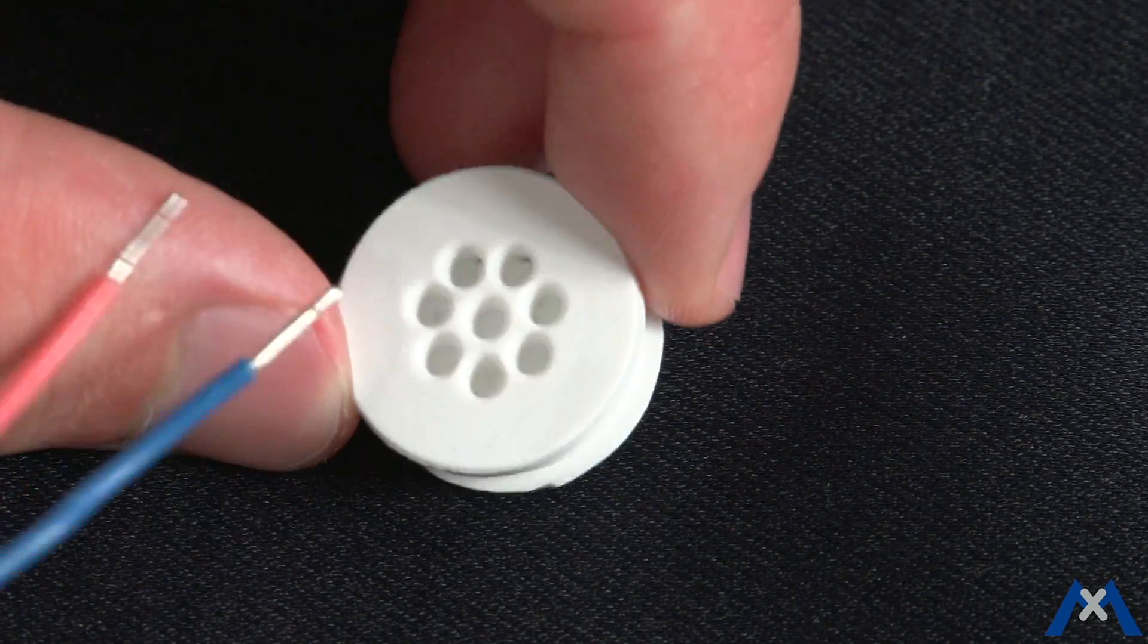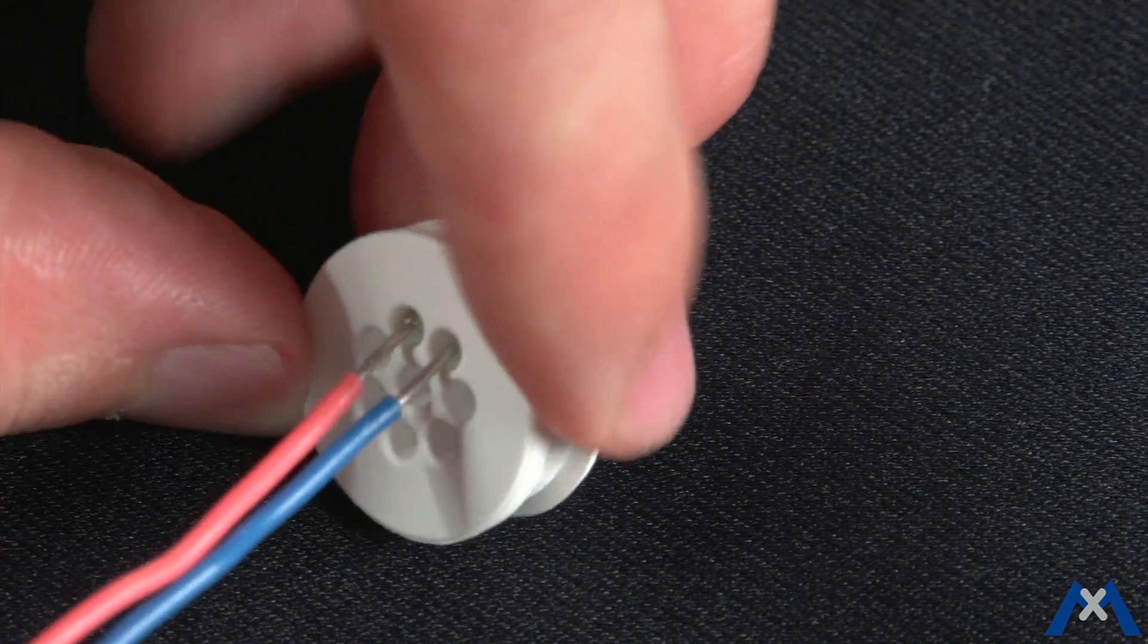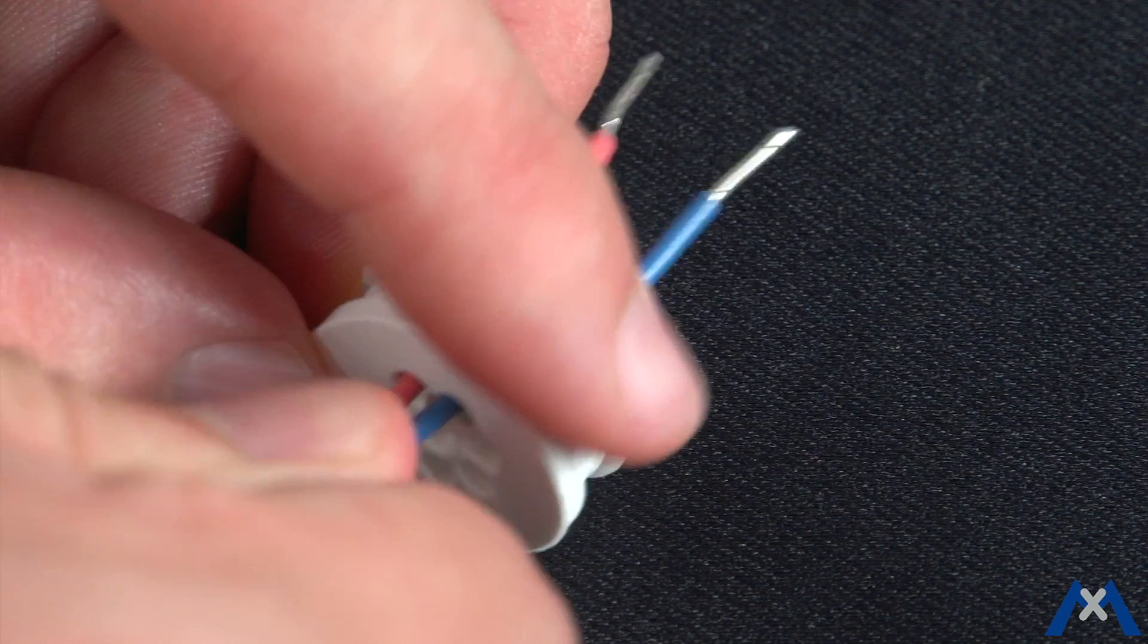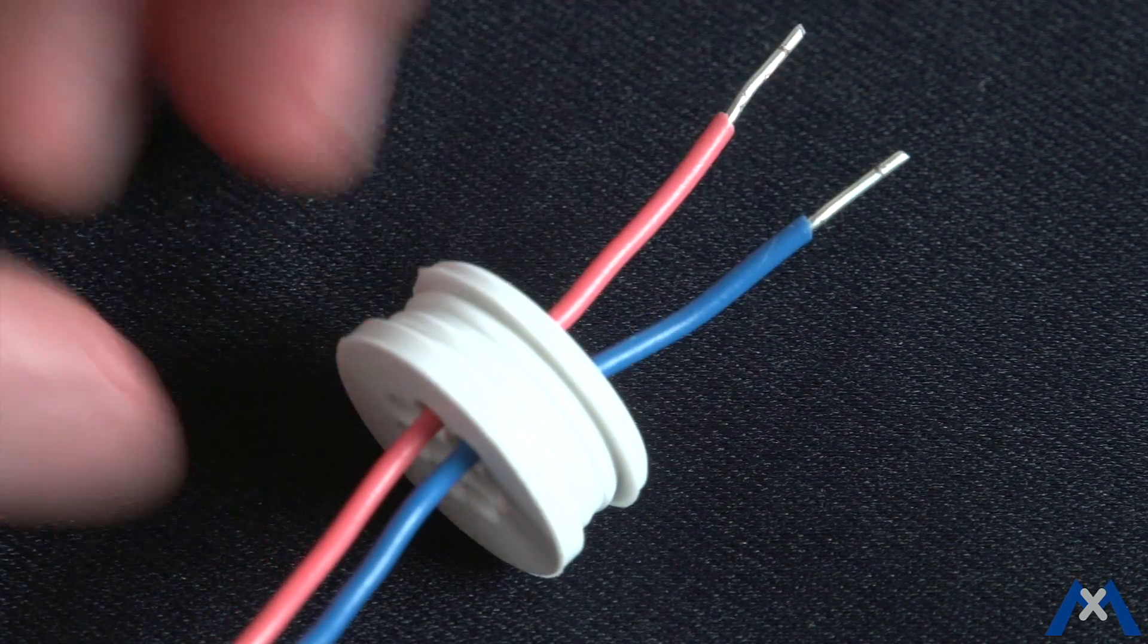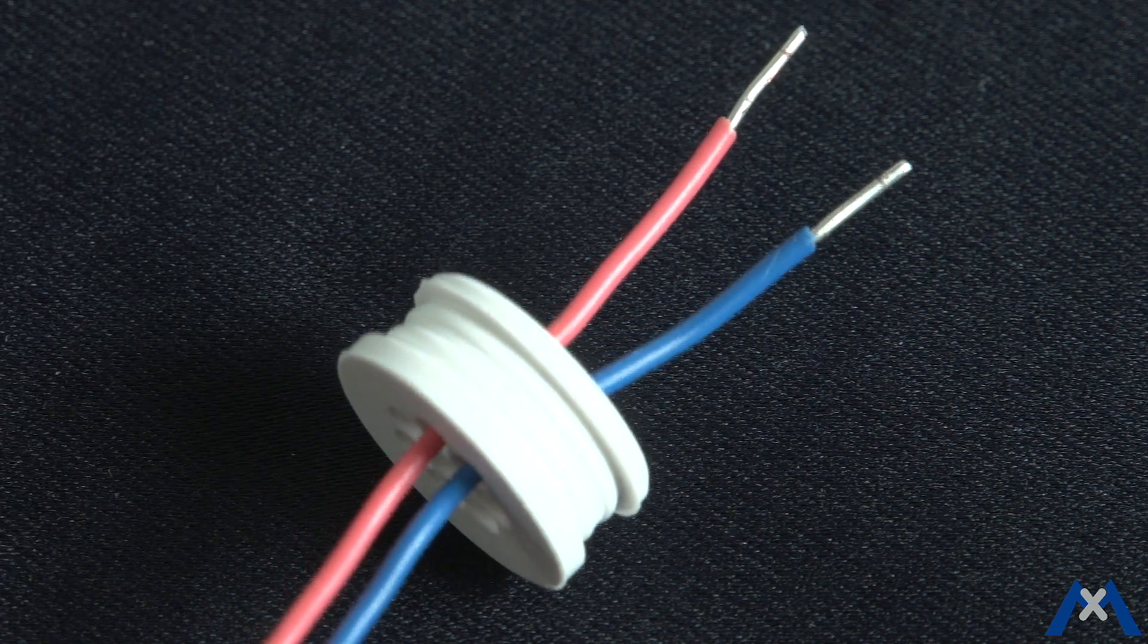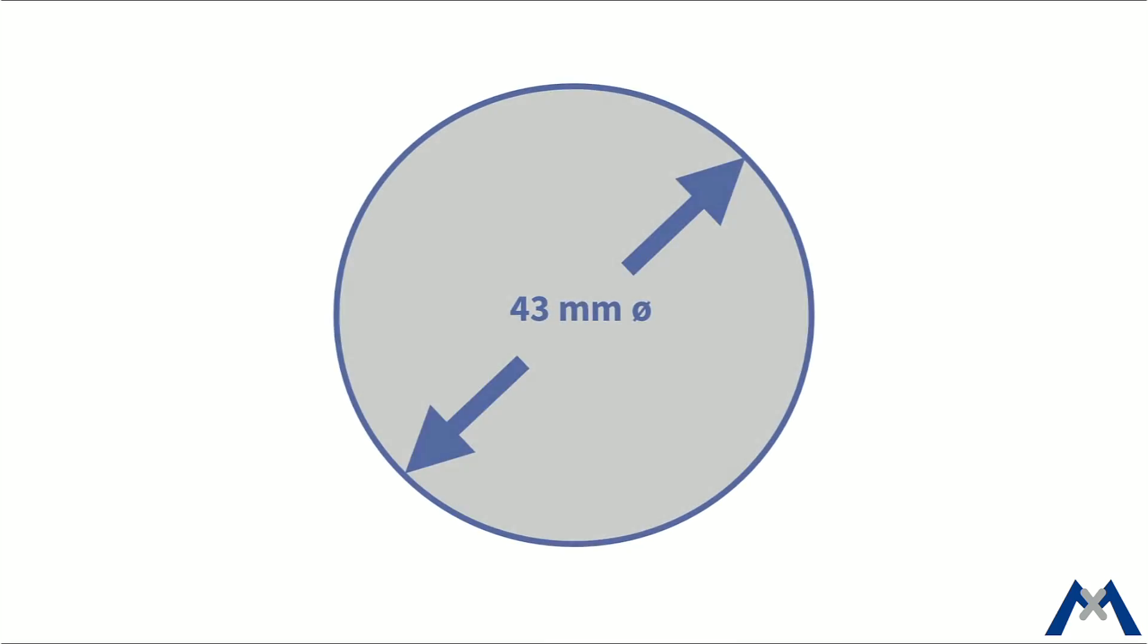If you are using the single wires, push them through the single wire plug. If you want to install the module in cavity walls or covers, you need to drill a hole with 43mm diameter at the position where the Multisense will be installed.